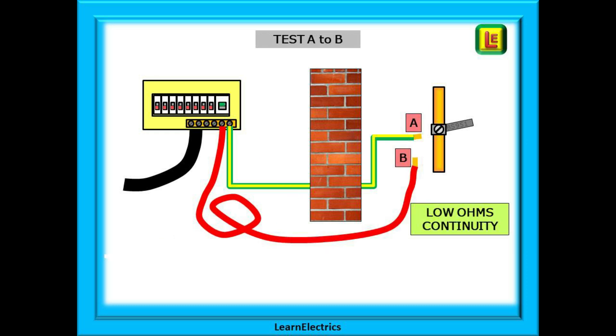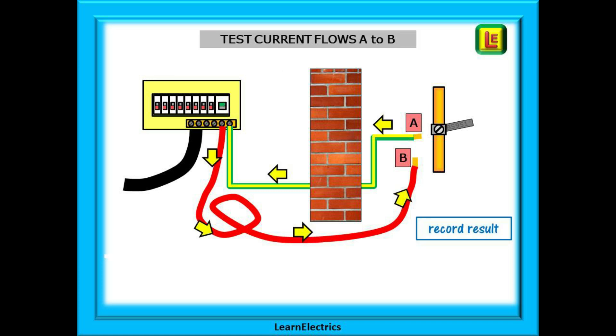Now take one end of the wander lead through to the garage or wherever the water pipe is. Connect your meter clips between points A and B and make a low ohms continuity test. Test current will flow from point A to the main earth terminal on the bonding conductor and back along the wander lead to point B. If we get a suitably low reading then this proves that the bonding conductor is continuous and okay, and we should record the result.